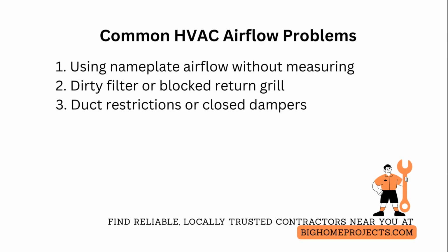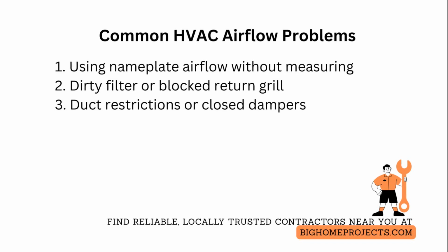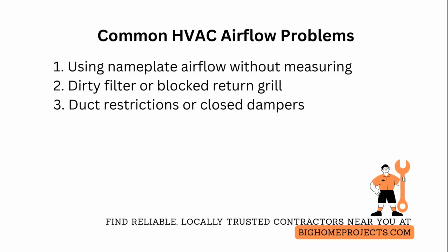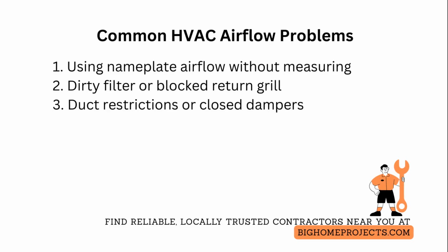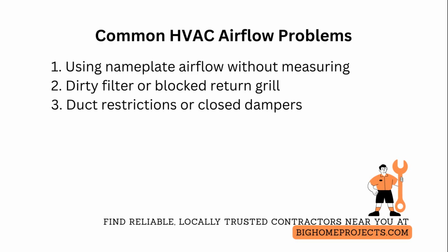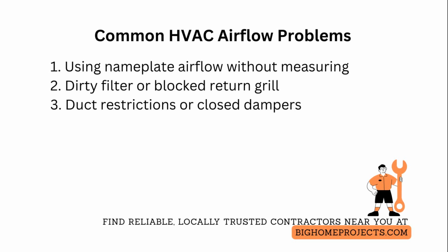One of the most common mistakes is relying on nameplate airflow or expected CFM without measuring actual CFM using the temperature rise formula and static pressure diagnostics, which leads to misdiagnosis. Fix it by performing steady-state temperature measurements, averaging multiple readings, and using rated heat output for calculation. Another frequent issue is assuming a clean filter, when in reality a dirty filter or plugged return grill is causing low CFM. Remedy that by removing and visually inspecting the filter, measuring static pressure across it, and replacing with the correct MERV rating and size.